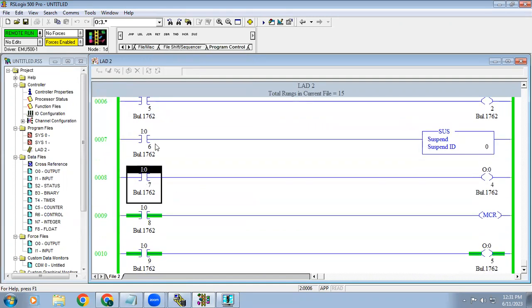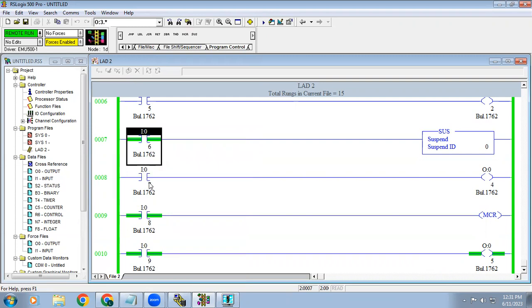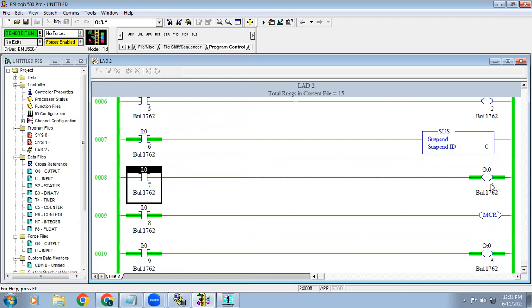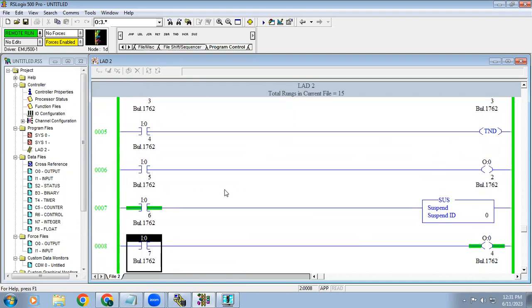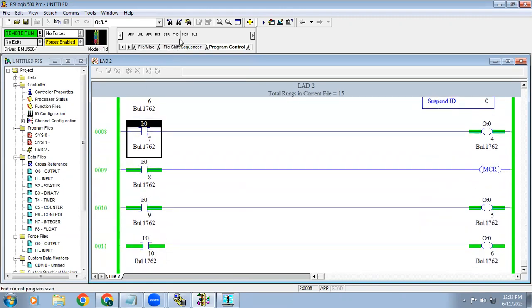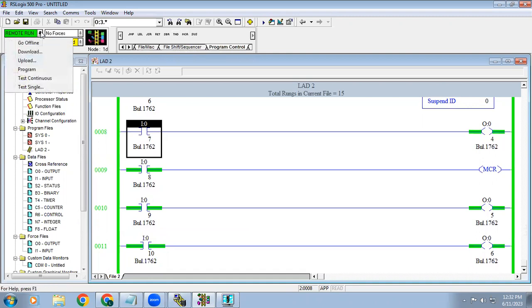Same goes for Suspend. Right now you can see it's working, but once Suspend is activated it won't work. When Suspend is deactivated it will work again. If the output is on and you activate Suspend, even if input is off it will maintain the on status — same as TND. The difference is that in real time, when you use Suspend, your PLC goes to fault mode. Once you deactivate Suspend then only it will work again. In simulation both behave the same, but in real time Suspend causes the PLC to go to fault mode.